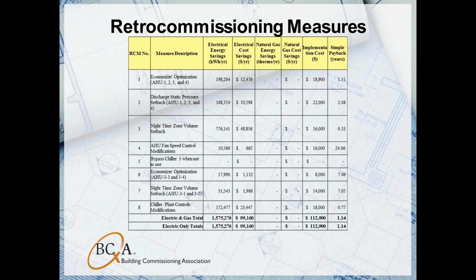With the fan speed corrected, we could now effectively implement static pressure reset out in the building. We typically do this by polling the VAV box damper positions and trying to reset the supply static pressure based on demand.